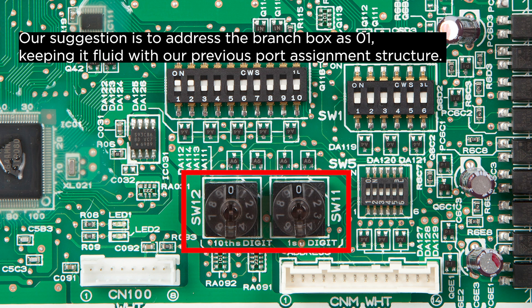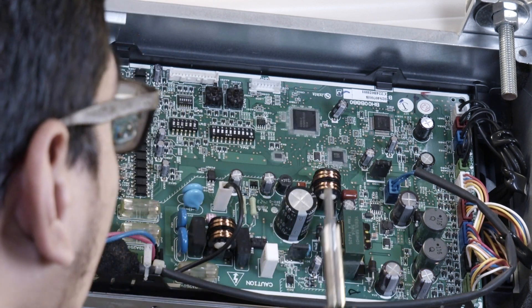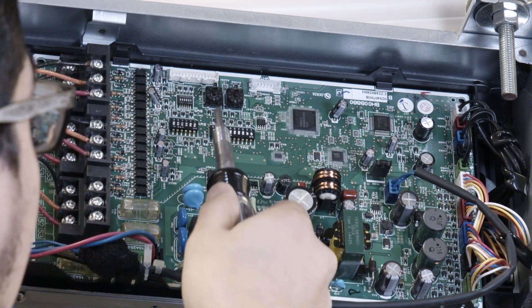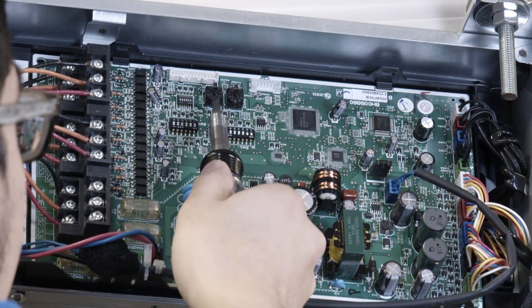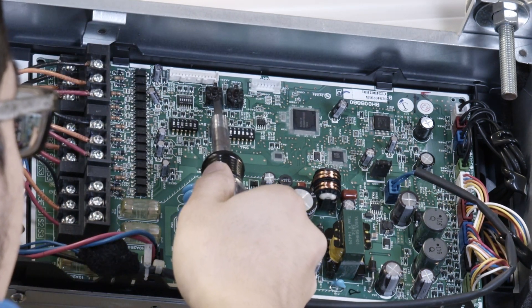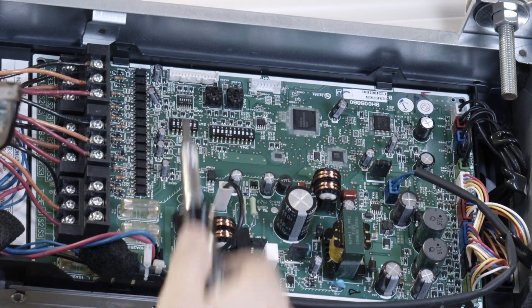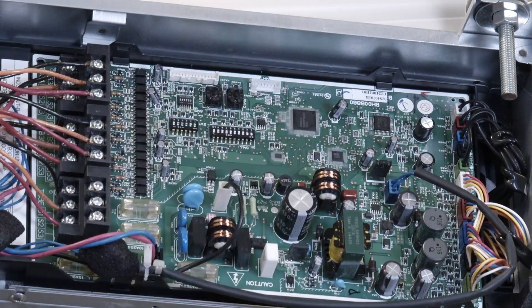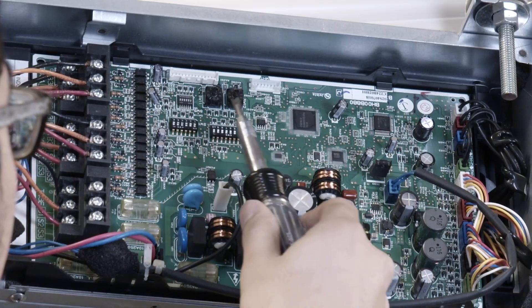Our suggestion is to address the branch box as 01, keeping it fluid with our previous port assignment structure. Keep in mind though this may change with more complicated systems. In order to set the branch box to 01, you'll need to set SW12 to 0 and move SW11 to the 1 position.